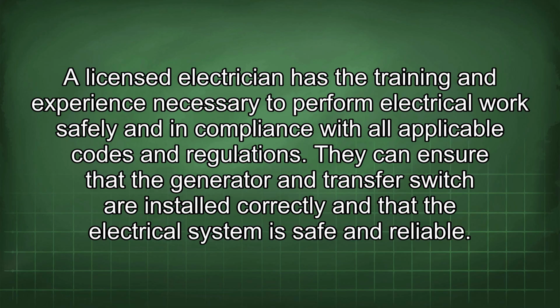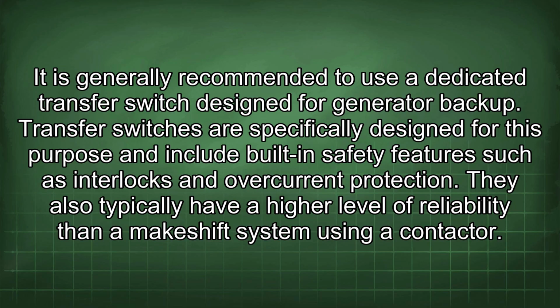A licensed electrician has the training and experience necessary to perform electrical work safely and in compliance with all applicable codes and regulations. They can ensure that the generator and transfer switch are installed correctly and that the electrical system is safe and reliable. It is generally recommended to use a dedicated transfer switch designed for generator backup. Transfer switches are specifically designed for this purpose and include built-in safety features such as interlocks and overcurrent protection. They also typically have a higher level of reliability than a makeshift system using a contactor.